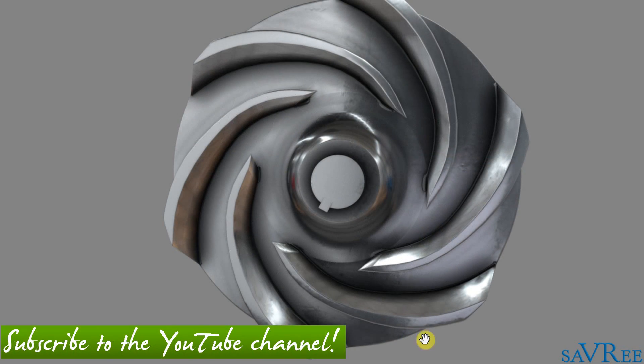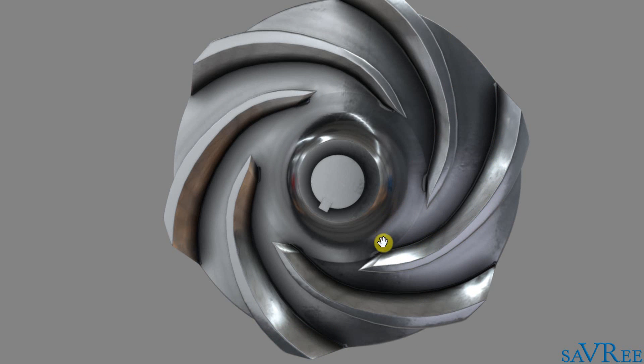So here is our impeller again. And we can see that the flow path area increases as the flow flows out radially away from the center of the impeller. And we know now that this increase in flow path is going to cause a reduction in velocity and an increase in pressure. And that is essentially how a centrifugal pump works.